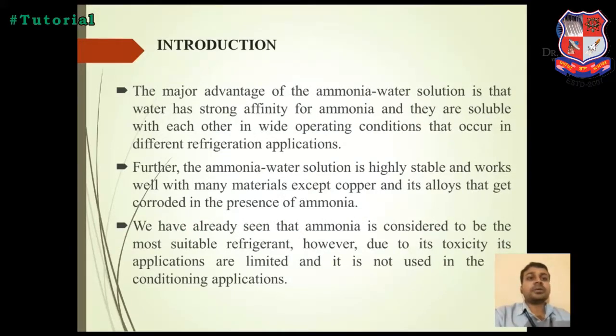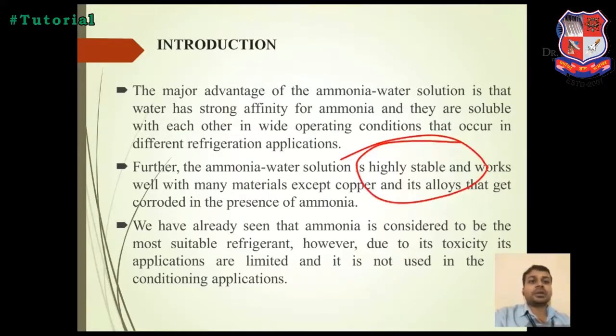Introduction. The major advantage of the ammonia water solution is that water has a strong affinity for ammonia and they are soluble in each other, with a wide operating condition that occurs in different refrigerant applications. Here the water is completely soluble in ammonia, and other refrigerants or absorber fluids are not completely soluble. This is the best mixture of ammonia and water solution, and also a highly stable solution, working well with many materials except copper and its alloys, which are corroded in the presence of ammonia.